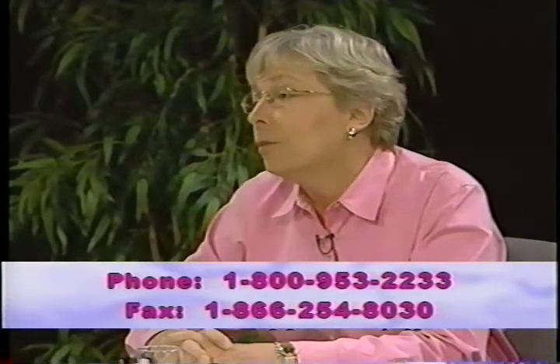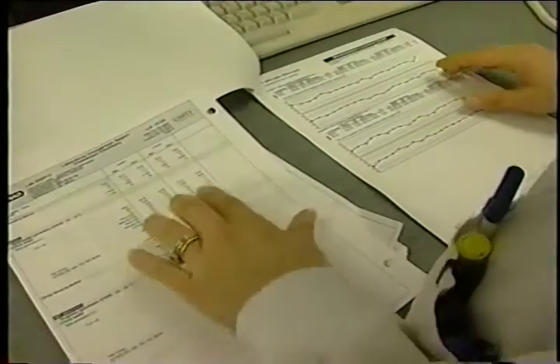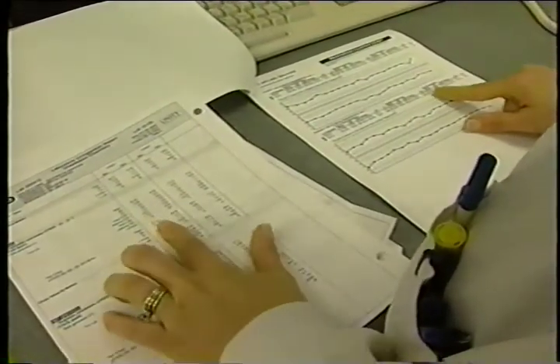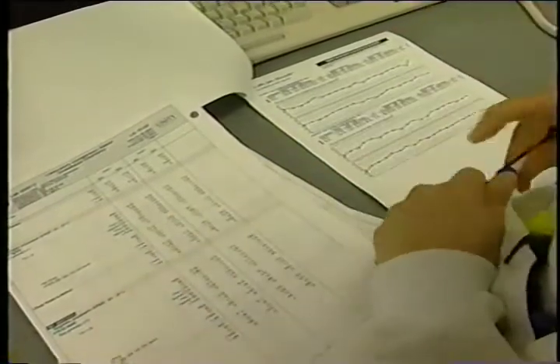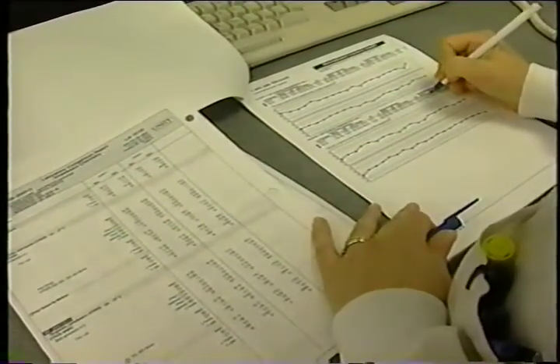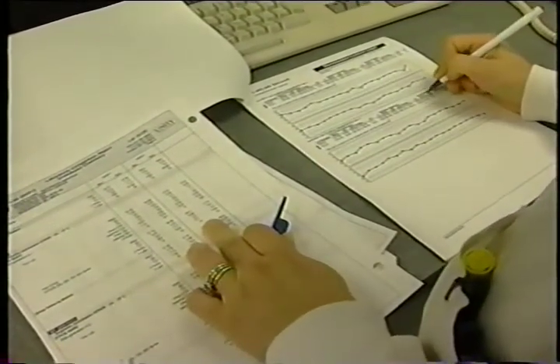These errors could be caused by test system failure, by extremes in the laboratory environment, and also by improper operator performance. Now, changes over time in any of these sources of error may also adversely affect the accuracy and precision of the test system. Because of this, the laboratory must also monitor the test system's control results over time, reviewing those results routinely for shifts and trends, as well as immediately at the time of testing.